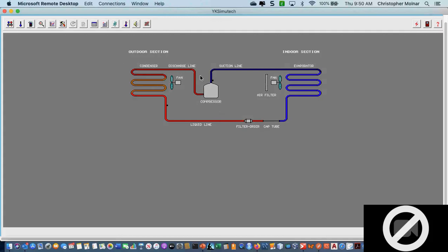My compressor is increasing the pressure, which increases the boiling point, and just through heat of compression — think about an air compressor, that air coming out is warm — I'm increasing the temperature. Anytime I push molecules together I increase the temperature. I'm coming out of the compressor with a high temperature, high pressure gas. I come into the condenser, which is the big coil you see outside. I'm blowing air across it that's about 35 degrees lower than the temperature of the refrigerant in the coil.